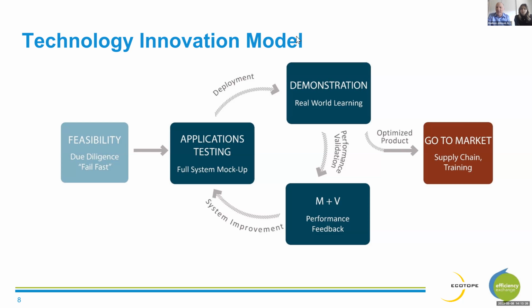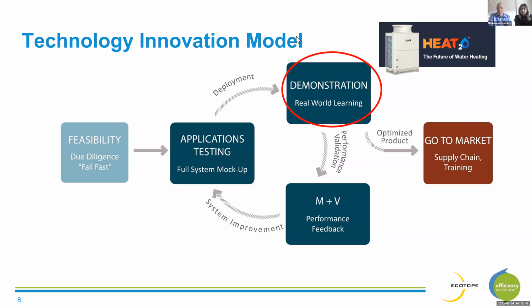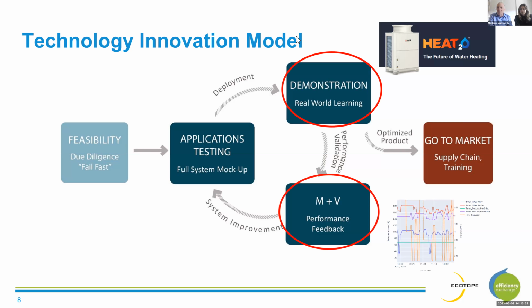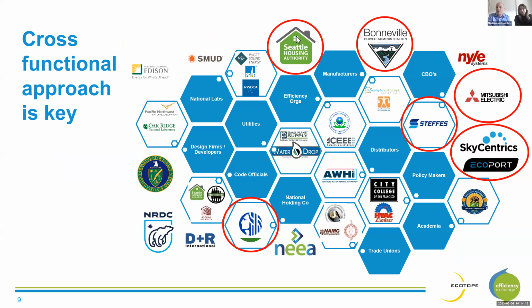So we go through a process of applications testing to make sure that all the other parts and pieces that are required to make the system work are integrated with that heat pump product before we bring it out to a demonstration. And this project at Bayview is the first demonstration of that Mitsubishi Heat2O commercial heat pump water heater product. And as we do that demonstration, we're doing detailed measurement and verification of the performance so that we can provide feedback to the manufacturer, validate our estimates of how well this thing is going to work in the field, and learn how to make that product better to roll it out into the marketplace. And this type of approach that we've been developing really requires a lot of different partners.